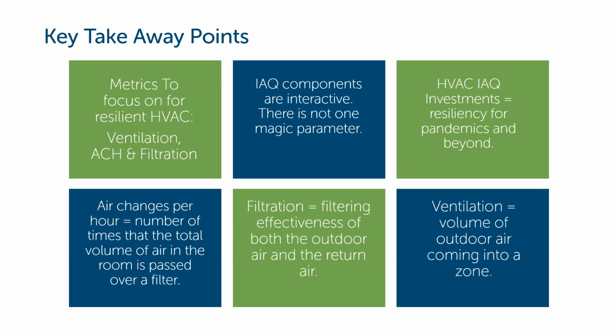There is one question that came in, and it says, how do you address upgrading the filtration when you don't have a separate set of OA or RA filters in a unit? There's only one mixed air filter. Yep. So what I think this question is getting at is we hear about the need to increase filtration on return air, but there's some equipment where you might not have two filter banks. Your outdoor air might be filtered with the same filter bank that your return air is filtered through.